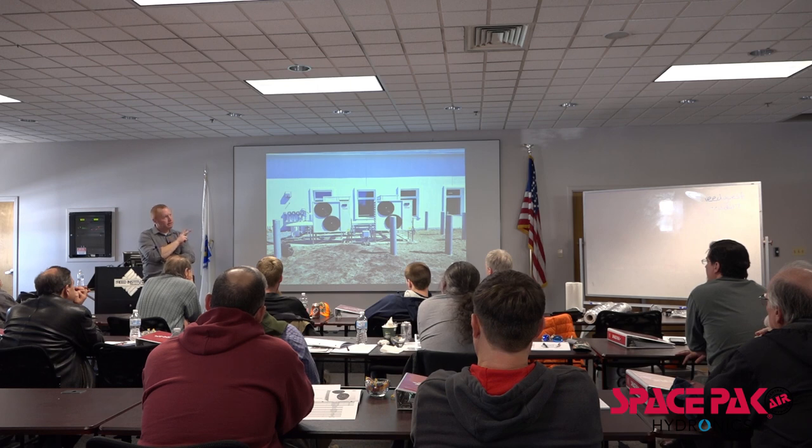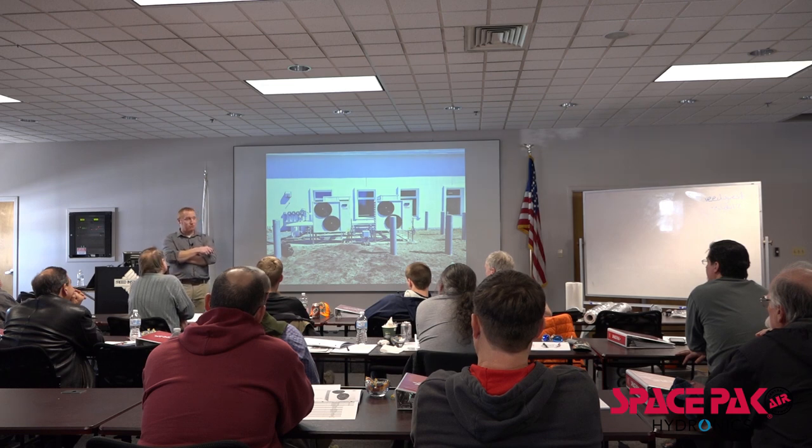Wind chill, this is on an old Air Force base up there, and they never shut off. Those two units never shut off. It kept the school from freezing and kept it at about 64 degrees. It was only making 70, 80 degree water out here because that's all it could do. It was negative 20, right?